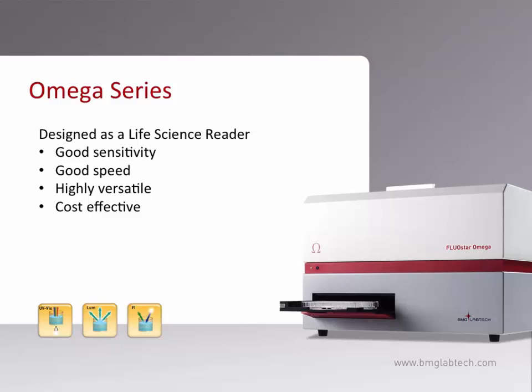Today we will be talking about the Omega series of microplate readers. This series is the most cost effective among our multi-mode microplate readers and can be equipped to perform absorbance, luminescence, or fluorescence intensity assays, or any combination of these detection capabilities. For the assay we will be talking about today, our focus will be on fluorescence intensity assays. The Omega readers exhibit good sensitivity at an LOD of 200 attomole per well for fluorescence, and can read a 384-well plate in as little as 16 seconds.